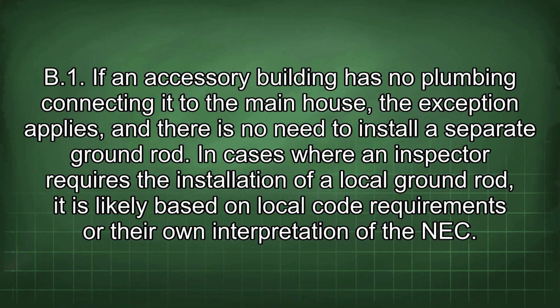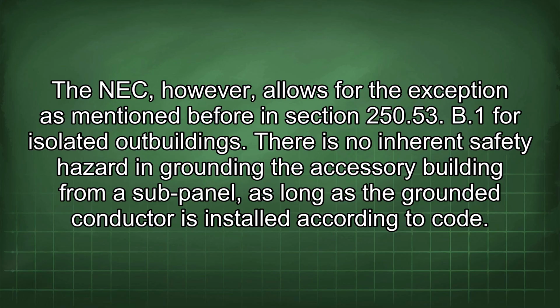(B)(1). If an accessory building has no plumbing connecting it to the main house, the exception applies, and there is no need to install a separate ground rod. In cases where an inspector requires the installation of a local ground rod, it is likely based on local code requirements or their own interpretation of the NEC. The NEC, however, allows for the exception as mentioned before in section 250.53(B)(1) for isolated outbuildings. There is no inherent safety hazard in grounding the accessory building from a sub-panel as long as the grounded conductor is installed according to code.